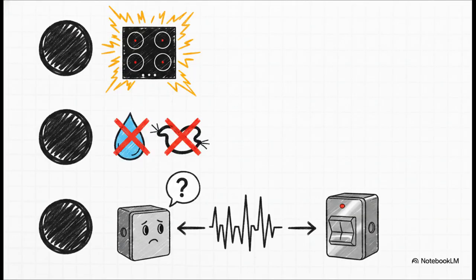There's no short and no broken coil. Well, sometimes it's just user error, like overloading the circuit by running 4 zones on boost mode all at once. But the really interesting part? That normal induction leakage we just talked about can completely confuse older Type AC breakers. The fix, at least in some regions, is upgrading to newer Type A breakers that are specifically engineered to handle the complex waveforms of modern inverter-driven appliances.